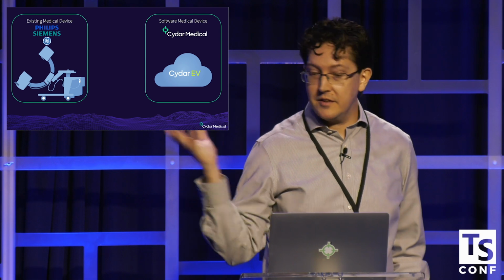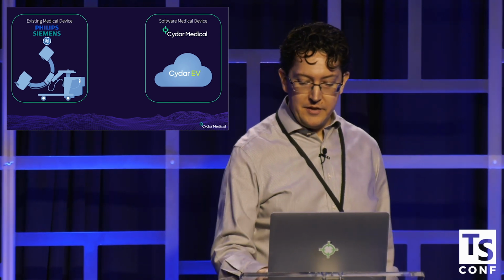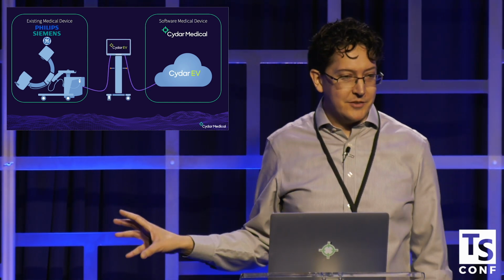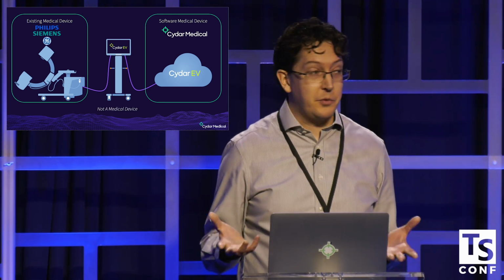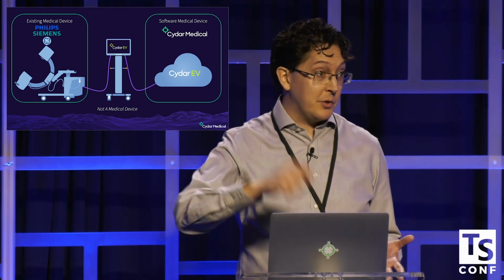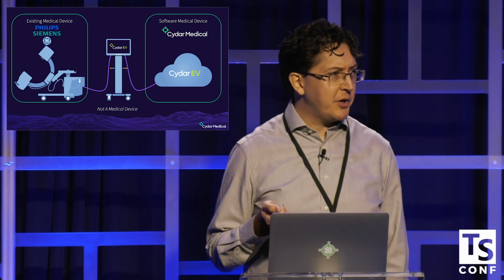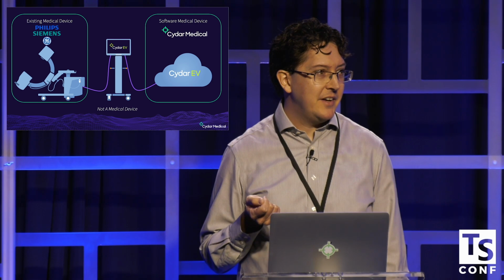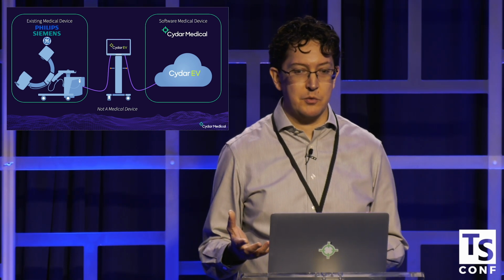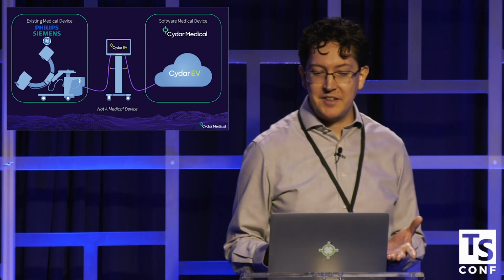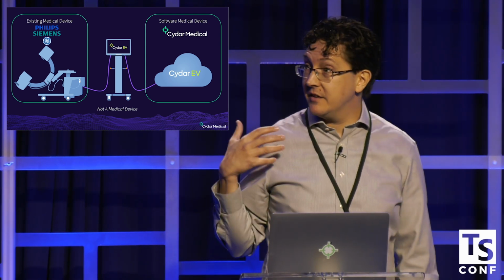In the middle, you have what we call a Cydar appliance. This is a standard PC running standard software. Therefore, that in itself is not a medical device. So this, we just get from a supplier. It has to conform to other standards, like the key one is it needs to be cleanable if it's in an operating room, which means it has to be fanless. That has a surprising impact on performance. If you compare the real-world performance of a fanless machine to exactly the same hardware but cooled, you'd be surprised at what a difference that makes. So that's something we've run into. But this is essentially a standard PC.